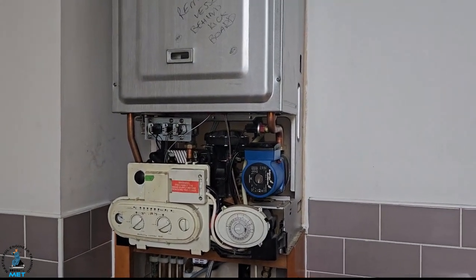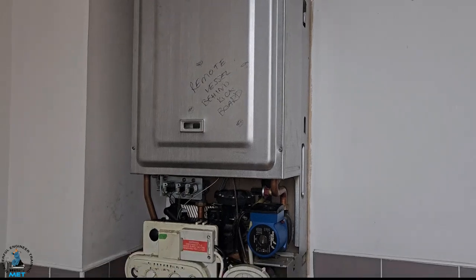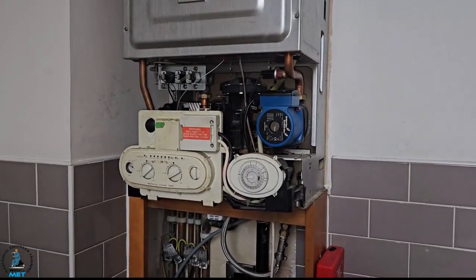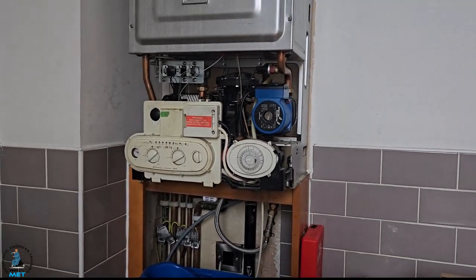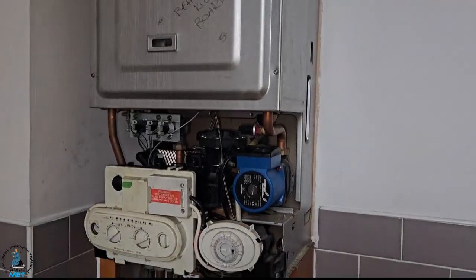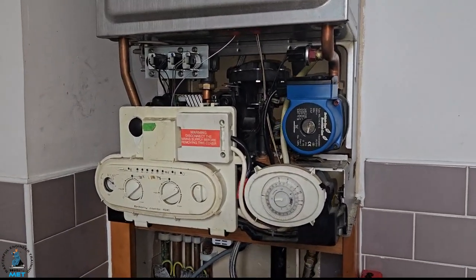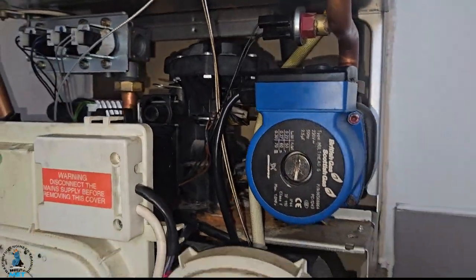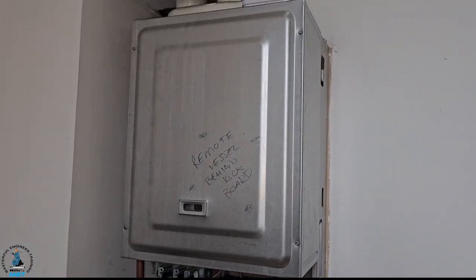Hi guys, it's Master Coach Tony Morgan and I'm with my son Myles Morgan. What we're going to do today is a massive job on this Chaffoteaux Britony Combi SE. We're going to change the main heat exchanger inside there — the plate heat exchanger — and change a diverter valve cartridge. I'm going to change this component here because basically this body is very, very old, which a lot of you guys will know.